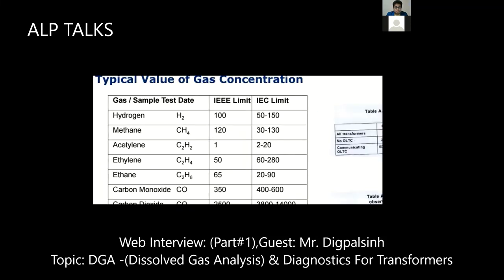Yeah, proceed. Then acetylene is 1 ppm and IEC has given 2 to 20 ppm. So there is a huge difference between these, because one is very small. But in the case of acetylene, you have to take note. As per my experience, it should be less than one. I don't know why IEC has given 2 to 20. But if acetylene is more than 2, then there is some kind of arcing. Minor arcing, but some arcing is there. So I think acetylene should be less than 2 or 1. Yes, because that is the main fault indication, the arc indication.